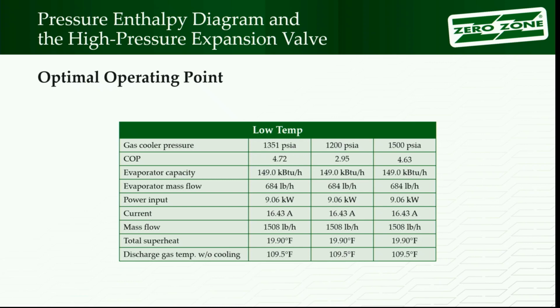When I went to the higher one, 1500 psi, COP is still not as good, right? Software says, no, you should have stayed at that 1351. So the rest of these items relate to the low temperature side of the system. You see any differences? Yeah.